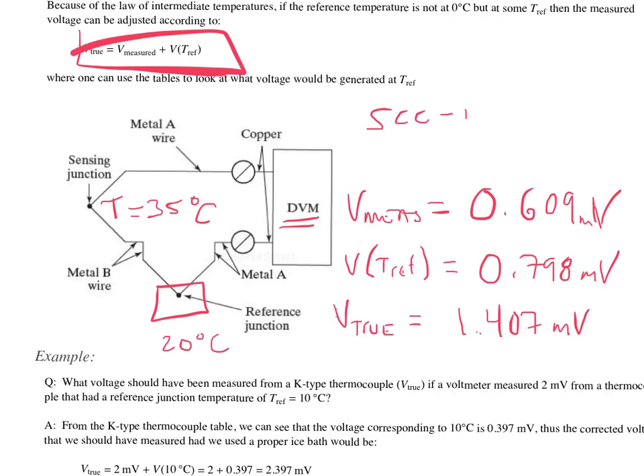This is done electronically. There's no ice baths in our labs upstairs. And so what LabVIEW will do is these modules have a thermistor inside them that will measure the reference junction and electronically compensate for not having an ice bath such that the voltage we output will be a corrected value. This is why when you select or choose a thermocouple in LabVIEW, there's different cold junction compensation options in the settings. And one is a built-in value, which means use a thermistor to correct for the voltage. You could also use an external source. We can use another thermocouple or some other temperature measurement device to measure the reference junction to correct for the value.